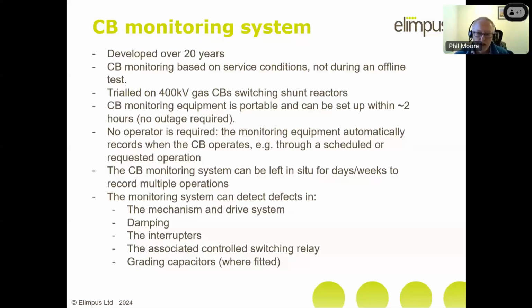Since most shunt reactors operate quite regularly, maybe every day or so, you can put this on, maybe leave it in situ for a few days or a few weeks. You ideally want to record about 10 operations. That gives you a pretty good feel for the way that the circuit breaker is behaving. And we can detect defects in the mechanism and the drive system, the damping, the interrupters, the control switching relay, and the grading capacitors. And you now see why I did all that CB theory stuff, because if we hadn't done that, you might not have entirely got the idea of what these points are.